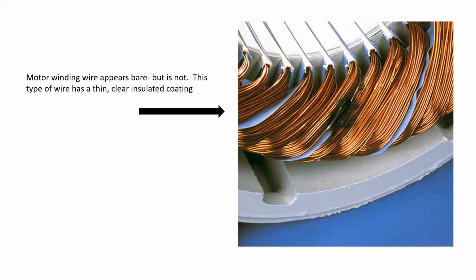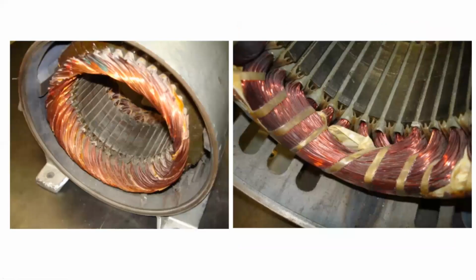Now, this motor winding wire appears bare, but it's not. This is a type of wire that has a thin, clear, insulated coating over top of it that's invisible to the naked eye. You can see here in this picture, there's actually been some damage to this particular wire, probably from an overheating condition. The finished assembly looks like this, and the rotor nestles right in this area, so there's barely enough room for a sheet of paper to go between the rotor and the stator's core. All of this is then dipped into a resin mixture that solidifies everything so that there is no movement due to magnetic flux or mechanical vibration. Because if these windings get damaged, the motor is effectively dead.